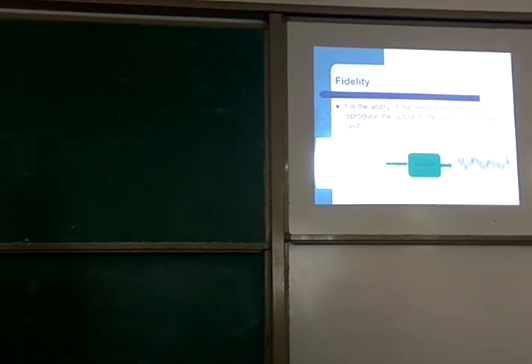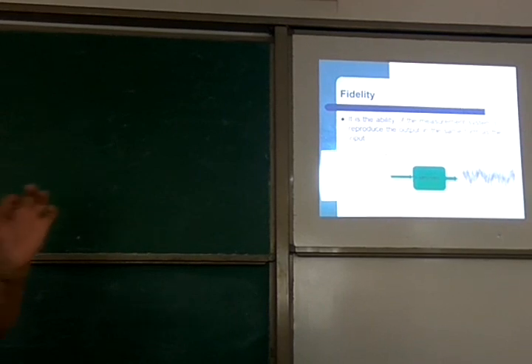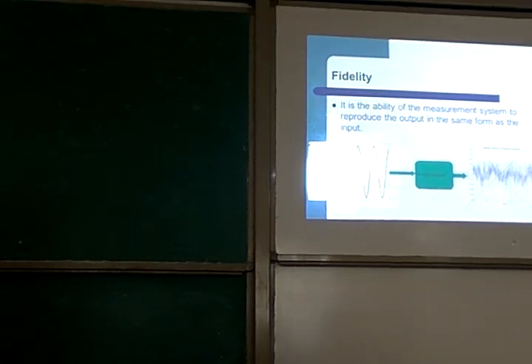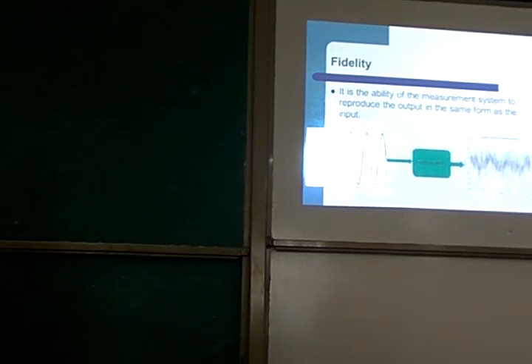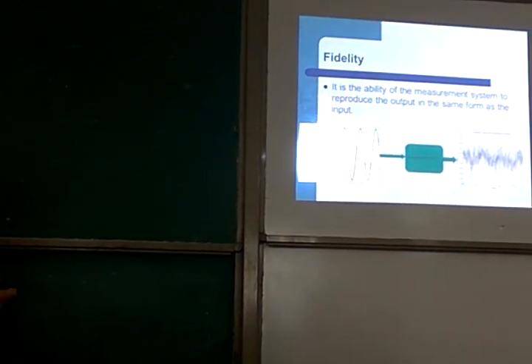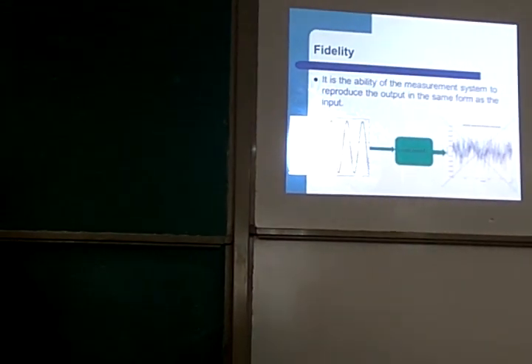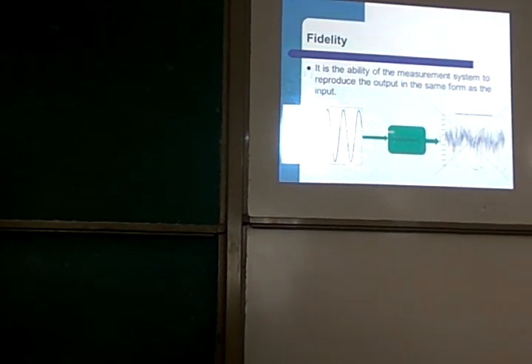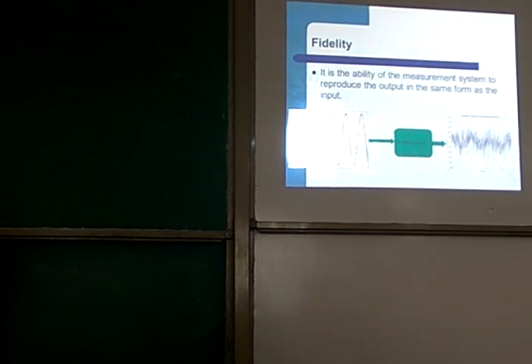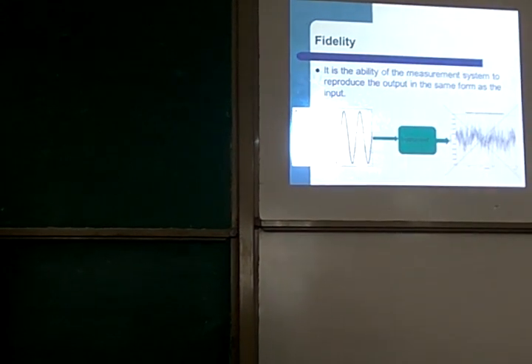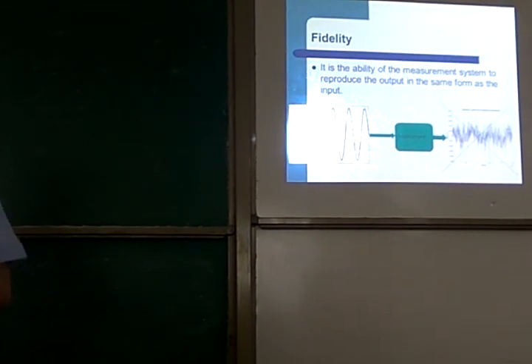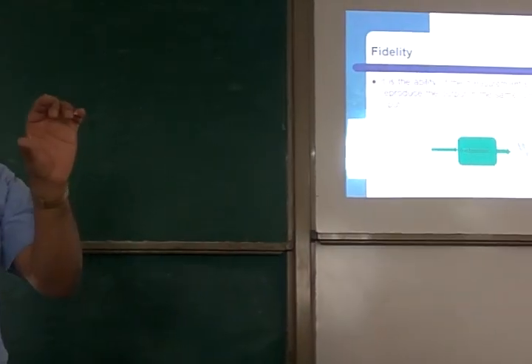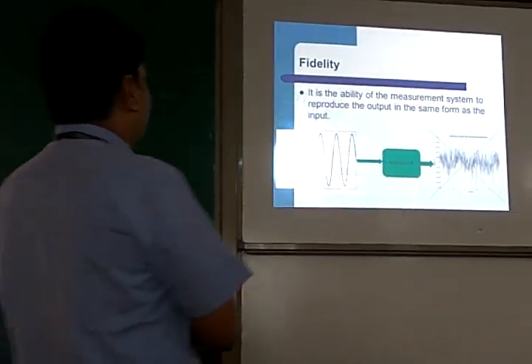Many times we try to identify a number as the result of measurement — for example, temperature: 50 degrees Celsius, where 50 is the number and degree Celsius is the unit. But in certain measurements, the waveform itself is the result of measurement, for example when we measure acceleration, vibrations, or audio signals. In those cases, the signal itself is the result. We may extract many parameters from it. So in those instruments, fidelity is very, very important — the instrument must not distort the shape of the input signal.